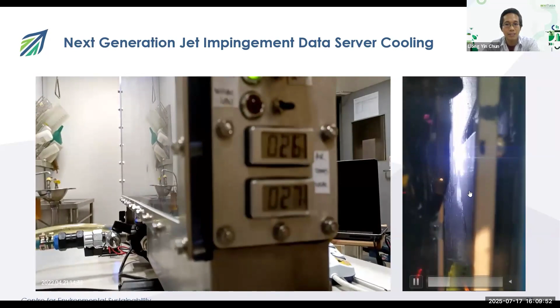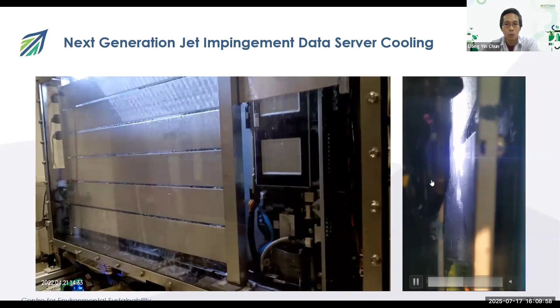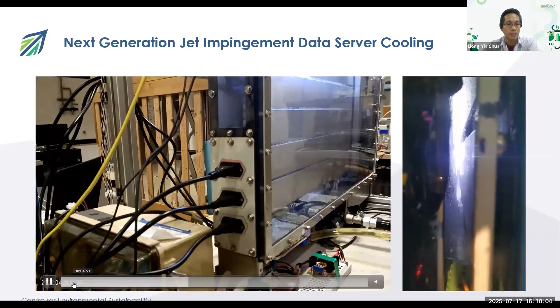We design this spray plate and place it next to the motherboard. As the system starts, it sprays coolant on the motherboard evenly everywhere. The good point of this system is that we drastically reduce the amount of coolant needed. For immersion cooling, you have to submerge the entire motherboard up to this height, but for our system, because we are just spraying, we only need a small amount of coolant at the sump, at this reservoir, to circulate and cool it down.